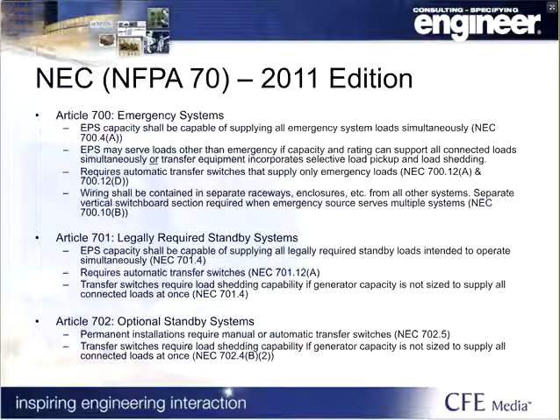All three systems are required to have transfer switches. Emergency transfer switches must be automatic and serve only emergency loads. Legally required standby transfer switches must also be automatic but are not required to be dedicated. Optional standby transfer switches may be manual or automatic.